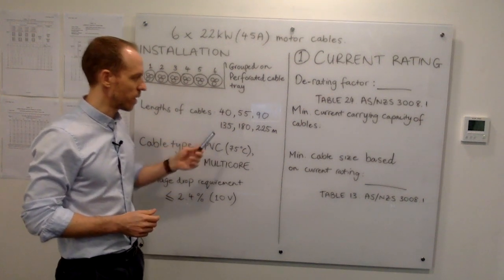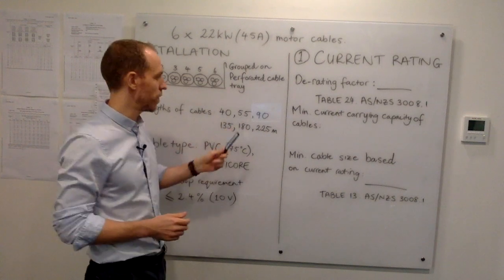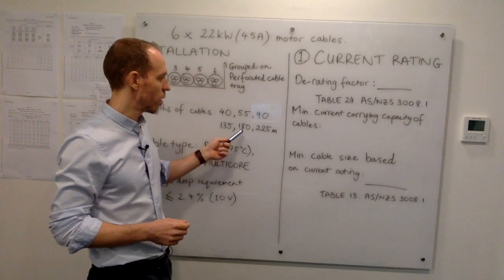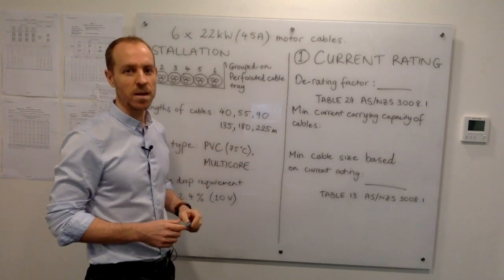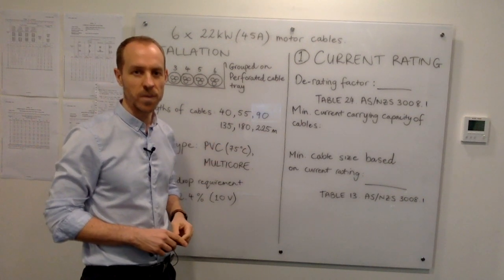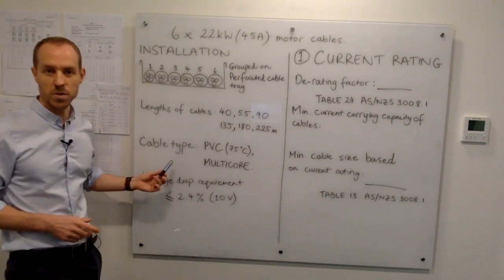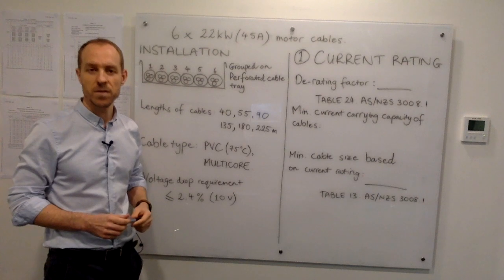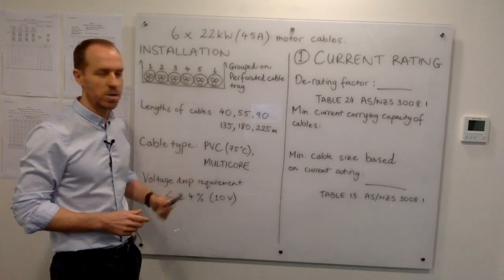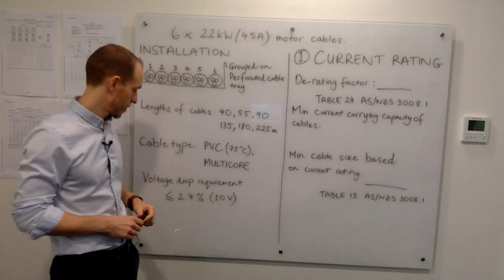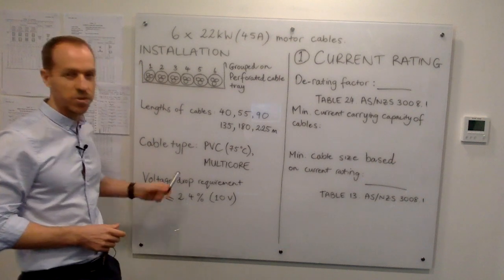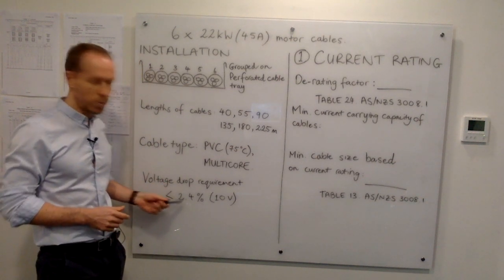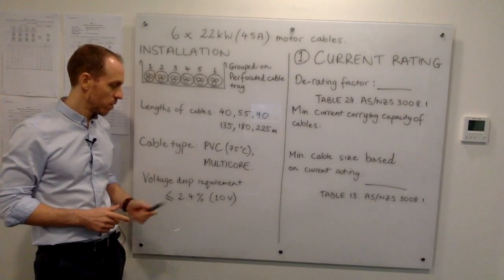These motors are located at different distances from the point of supply. We've got cable lengths of 40 metres, 55, 90, 135, 180, and 225 metres. The cables will be PVC type, 75 degrees, multicore. There's a voltage drop requirement of 2.4%, or 10 volts.